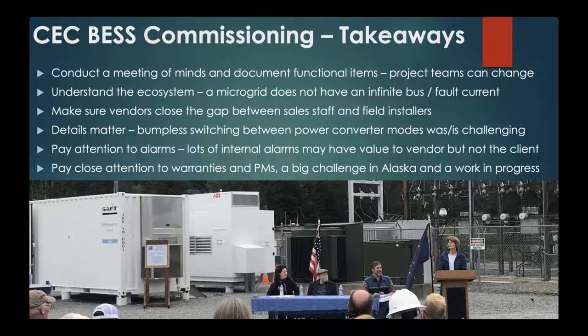For communications and handshaking, we absolutely insisted on Modbus RTU for our control signals. So when we're telling the battery to manually block load 200 kW, or if we want to balance our grid's power factor, which we've done, we can tell it to source 100 kVAR, then 200 kVAR, then 300 kVAR until our power factor is balanced.